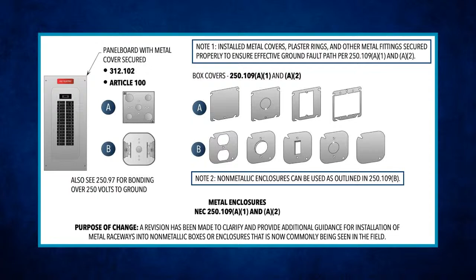So the first thing I did was isolate the circuit and found out the GFCI was tripping. I disconnected it and the GFCI held, so I reconnected it to see if it would work. What happened was the pool contractor was putting these switches in metal boxes and putting them in the covers. I told him I don't care, I'm just trying to see why the GFCI tripped, so what happened?